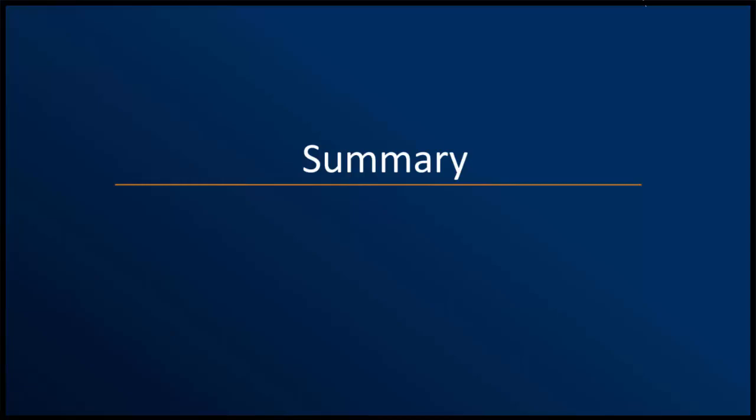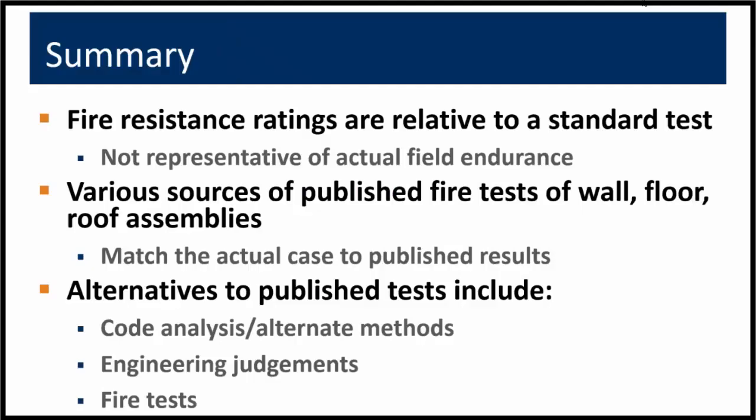In summary, fire resistance ratings are relative to a standard test. They are not necessarily representative of actual field endurance or the time on a clock in a real fire. Various sources of published fire tests of wall, floor, and roof assemblies exist and allow us to match the actual case to the published results. Alternatives to these published tests include code analysis, alternate methods, engineering judgments, and fire tests. We're also considering preparing another webinar on applying fire resistance ratings which establish the types of construction and relate them to the allowable heights and areas of the code. Please drop us a note or respond to the survey if you would be interested in such a part two on this topic.